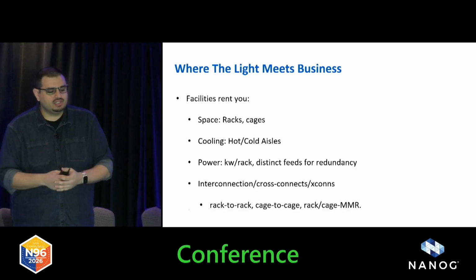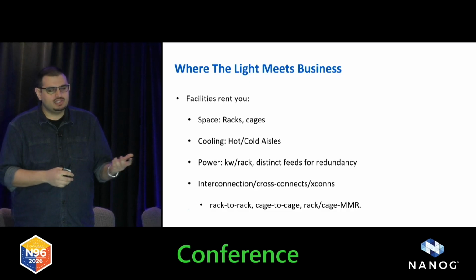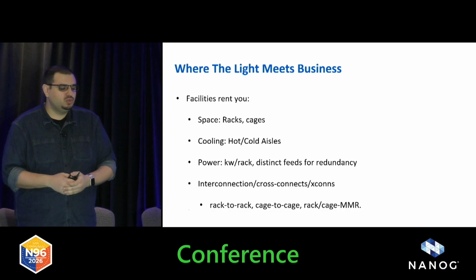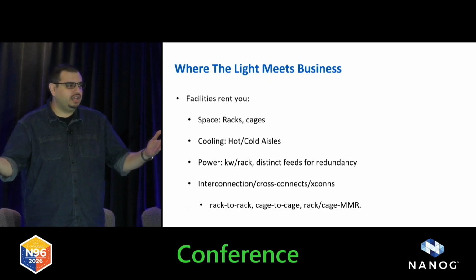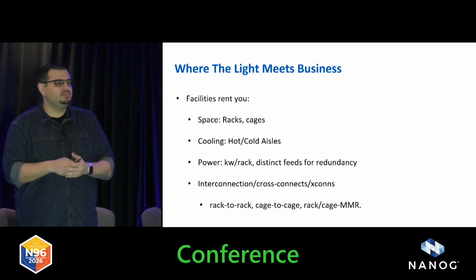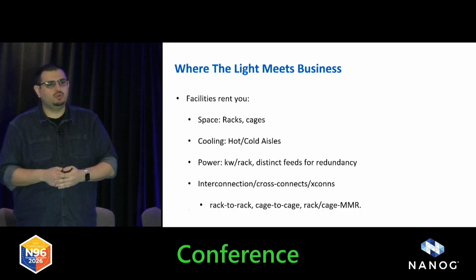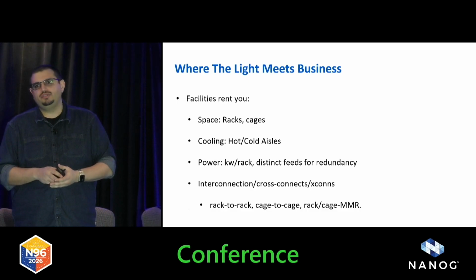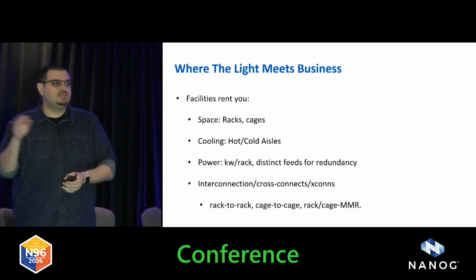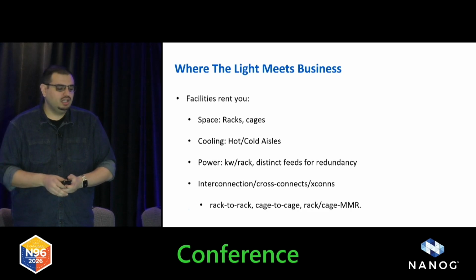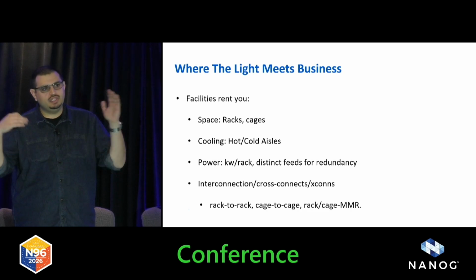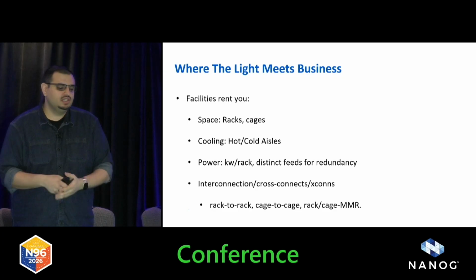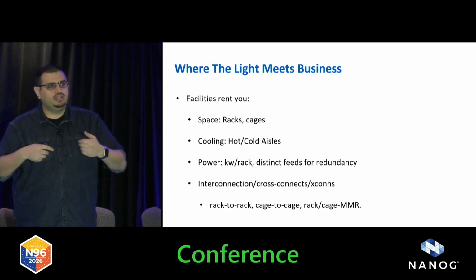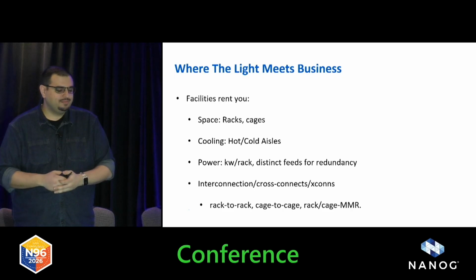Facilities rent you different things. An example of this is space, like racks or cages. Cooling, hot and cold aisles, are usually diverse, so when you're ordering hardware for these data centers, you need to know if your router should have front-to-back or back-to-front airflow, to align appropriately with the hot or cold aisles, bringing in cold air and exhausting hot air.